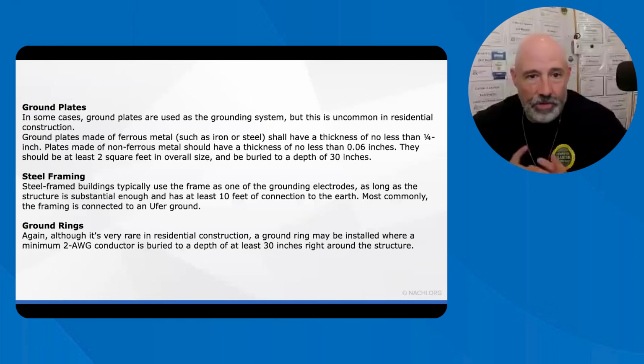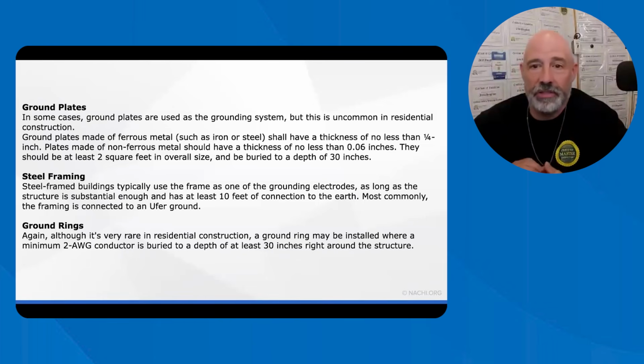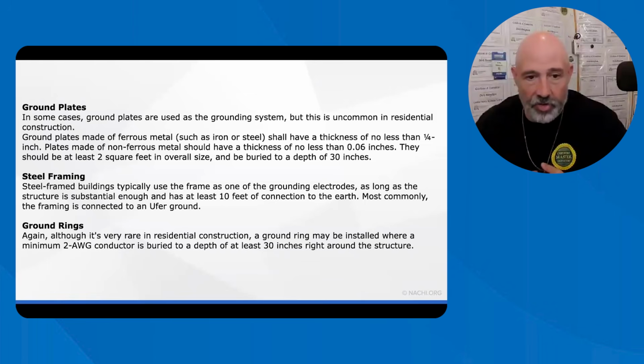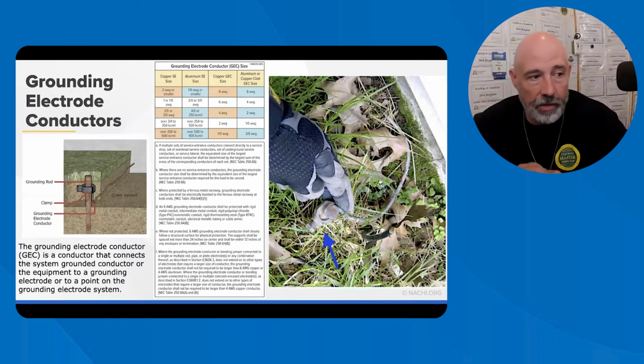So other grounding electrodes, you've got your grounding plates. They're uncommon in residential construction, but you can see them every once in a while in commercial buildings, but must be at least 2 feet square and buried at least 30 inches deep. Steel frame buildings must use the structural steel as a grounding electrode when properly connected to the earth. Ground rings are rare in residential applications and consist of 2 gauge conductors buried at least 30 inches deep around the structure. This is all good information that all inspectors should really just know and keep in their back burner. I feel like we've seen that before.